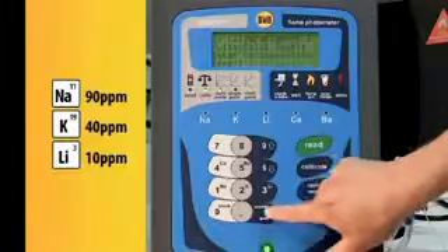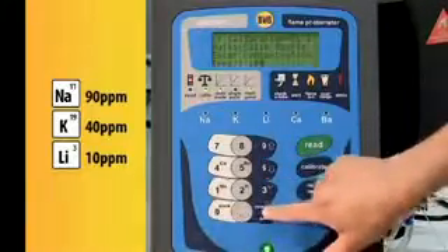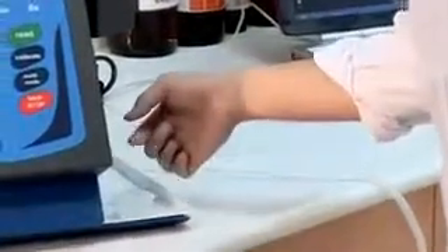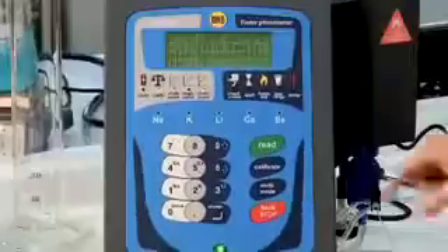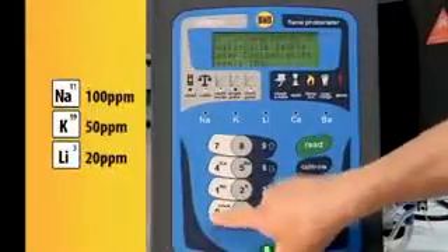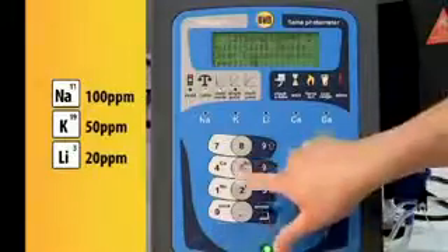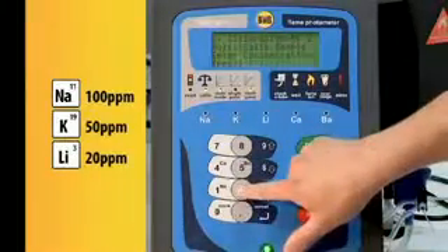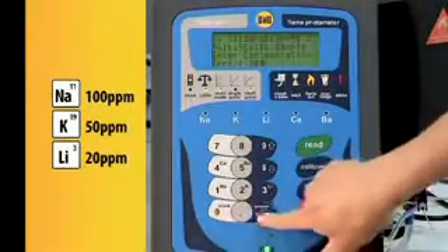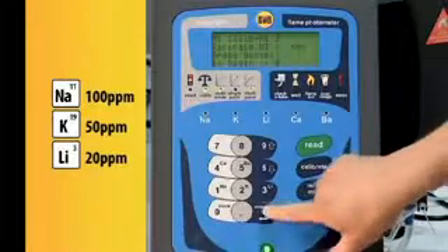We are prompted for a number of points, enter 3. Run the blank as before. We are now prompted for standard 1, sodium, enter 90. Potassium, enter 40, and lithium, enter 10. Aspirate standard 1 and key accept.